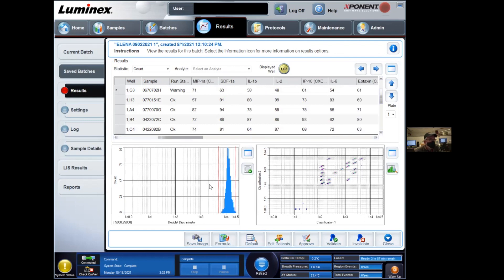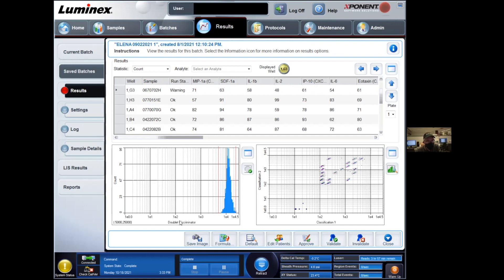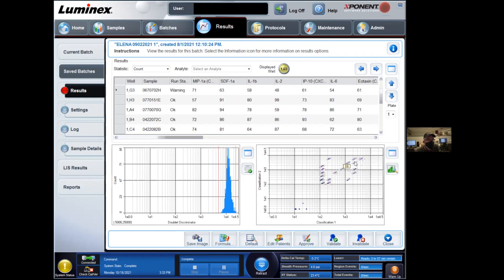At the bottom of the window, we find the doublet discrimination table. So these are the values we've entered at the beginning when we set up the experiment template. It should be somewhere between 5,000, 15,000, 25,000, depending. This is the peak of single cells. Anything below is typically just noise and debris. And the second graph, we have the classification one and two. So these are essentially different concentration of dyes for each of these beads that we're looking for. They kind of cluster together, as you can see, in really nice spots on the graphs. Each of them represents one of your analytes. And the tiny dots are each a single bead that has been measured.